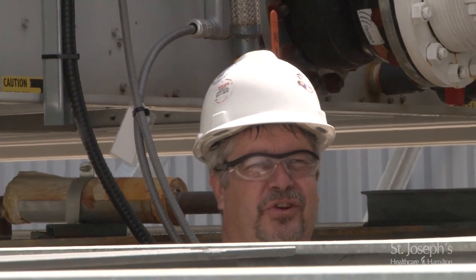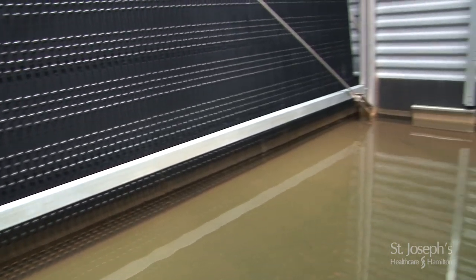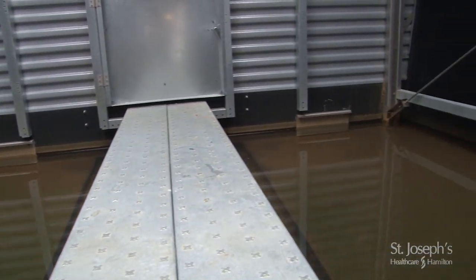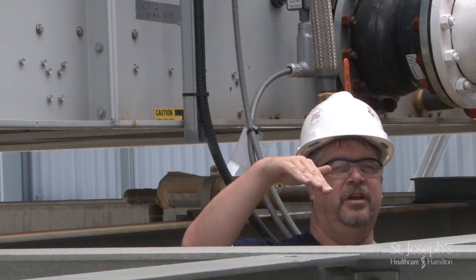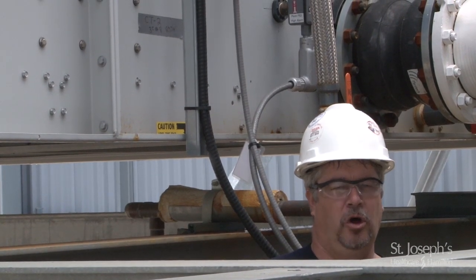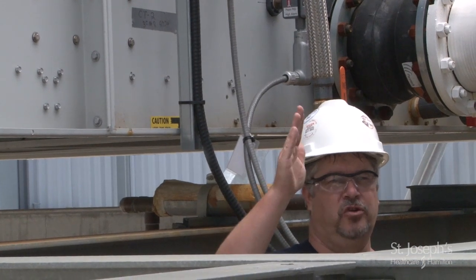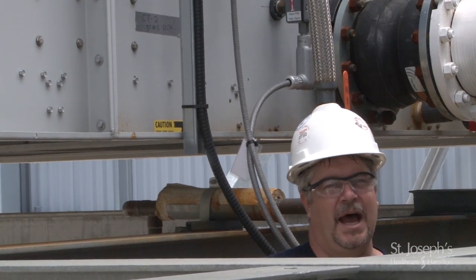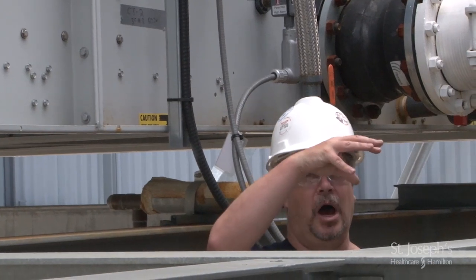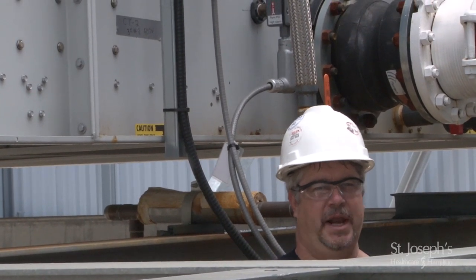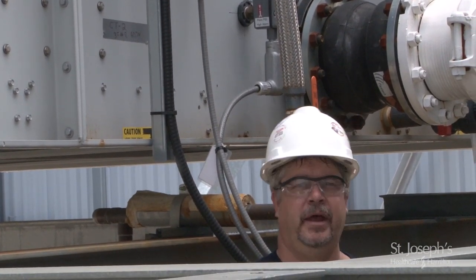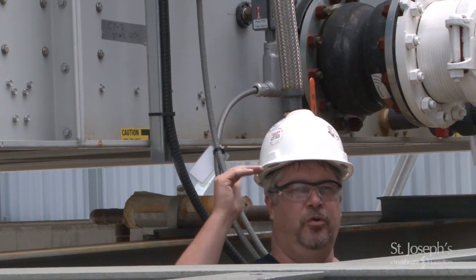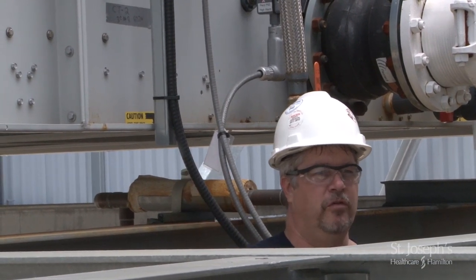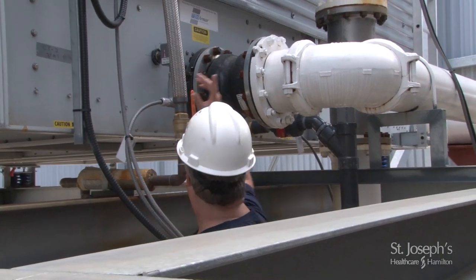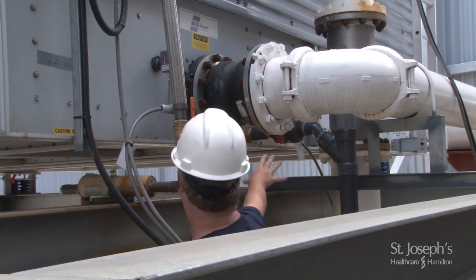This was an added feature to the cooling towers at St. Joseph's. It's a float assembly inside. As the water level rises, and if it reaches for whatever reason higher than normal operating levels, it'll trip that switch and send an alarm back to the building automation system to warn somebody, hey, cooling tower number 1 is operating at a critical level. It could overflow. We also have behind us here some gray piping.